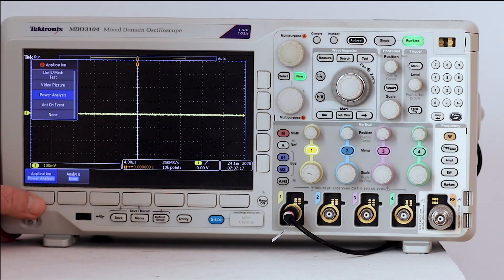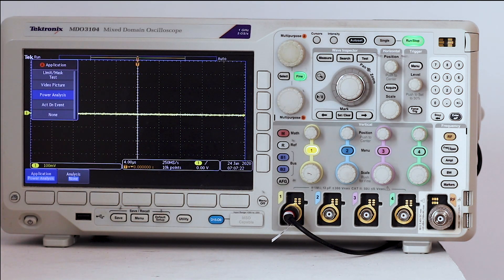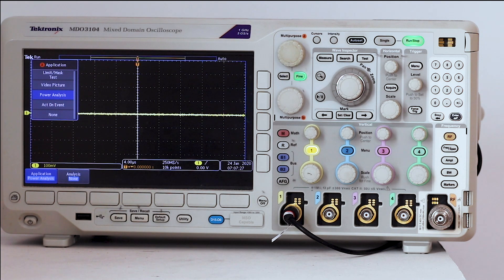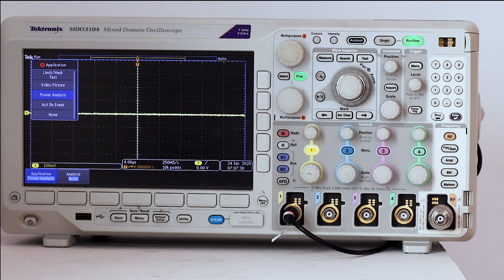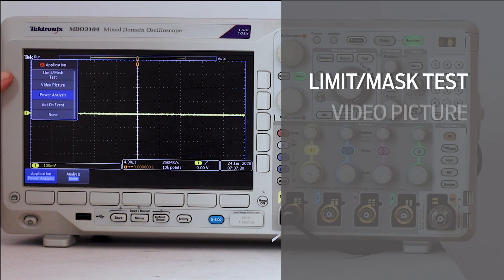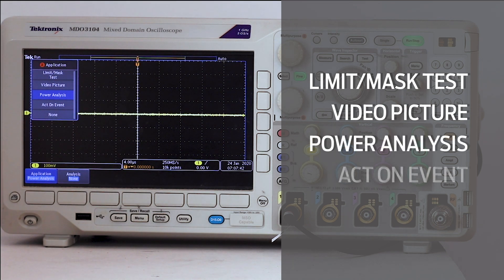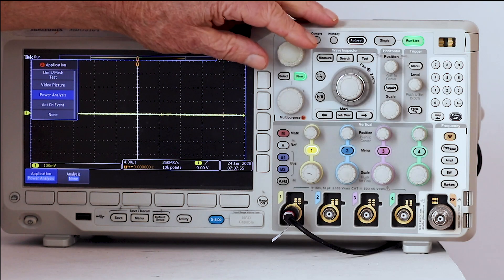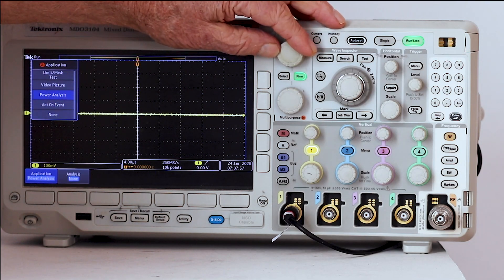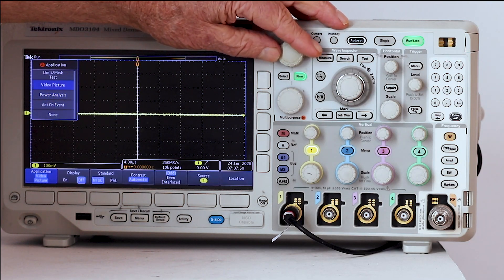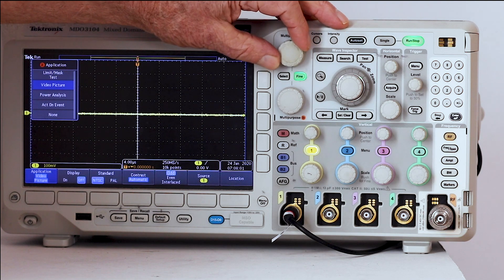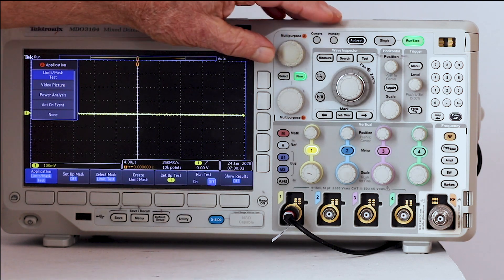This brings up the vertical application menu and the horizontal menu. Any of the available selections can be chosen by turning multipurpose knob A. The selections are limit mask test, video picture, power analysis, act on event, and none. Notice as you turn multipurpose knob A to scroll through them, the menu items in the horizontal contextual menu change.